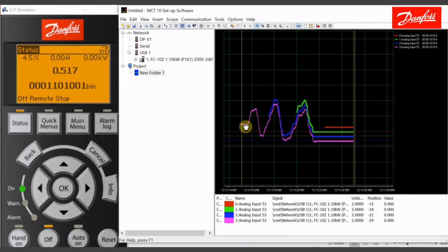13 years in tech support, occasionally the caller would say, my drive goes through the same process, same cycle all day, day after day. Sometimes it trips on, say, a DC link voltage, and most of the time it does not. Why does that happen? Well, it may be that always at that particular part of the cycle, it's close to tripping, but just doesn't. Using this and various rates, you can go back further and further in time to see a trend, and confirm that idea. Is that what's happening? Is it always close to the alarm threshold, but not just over?